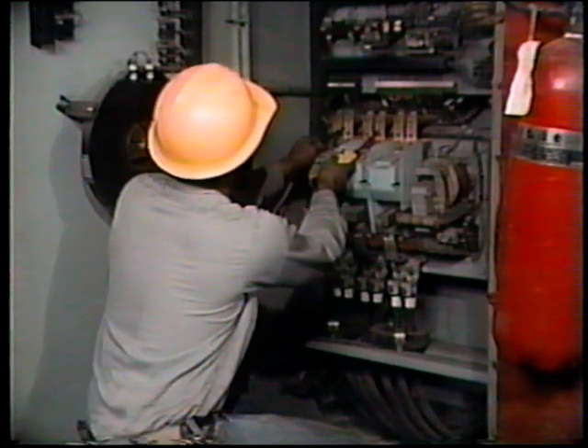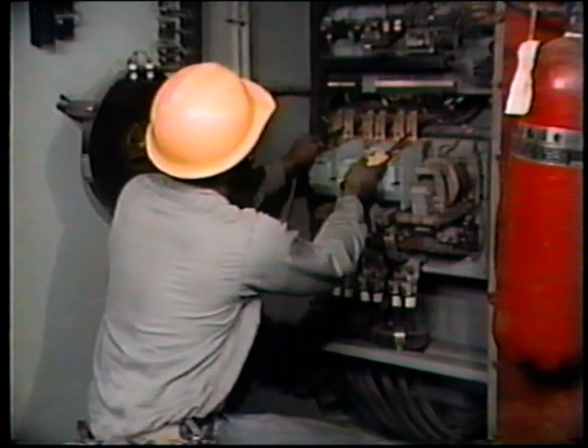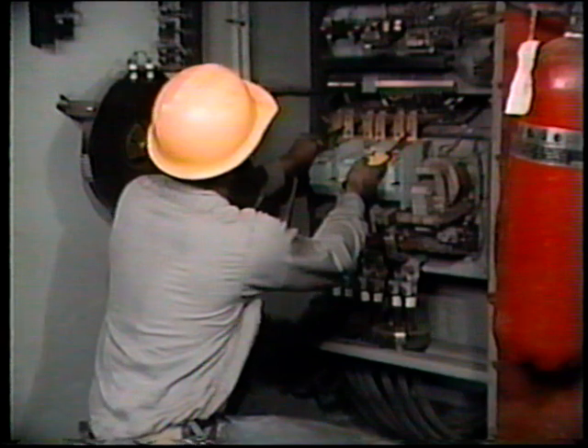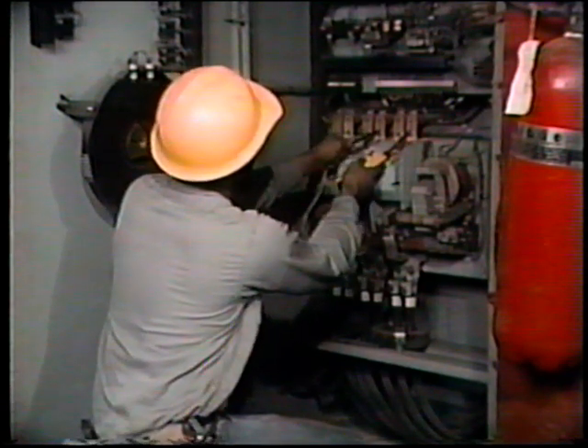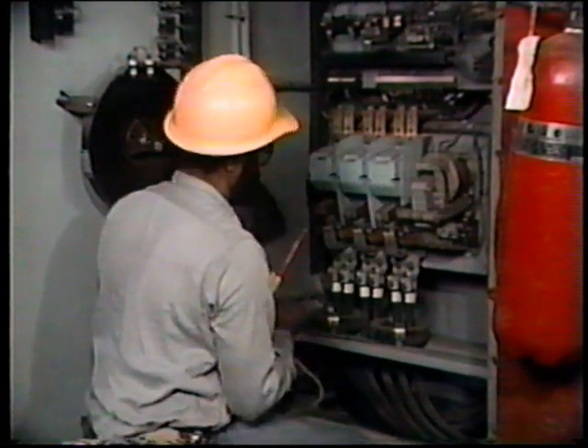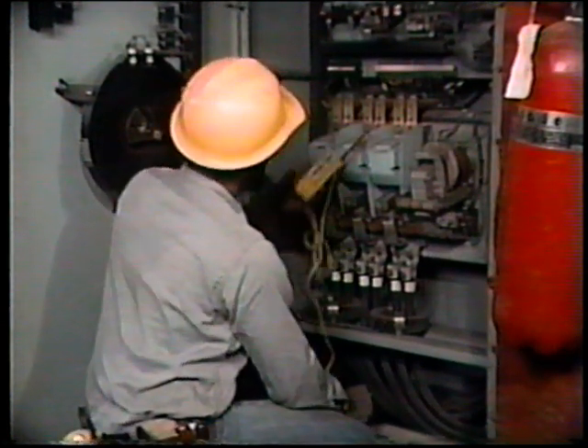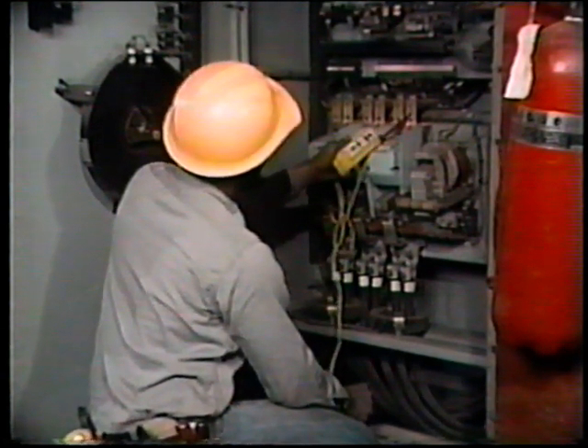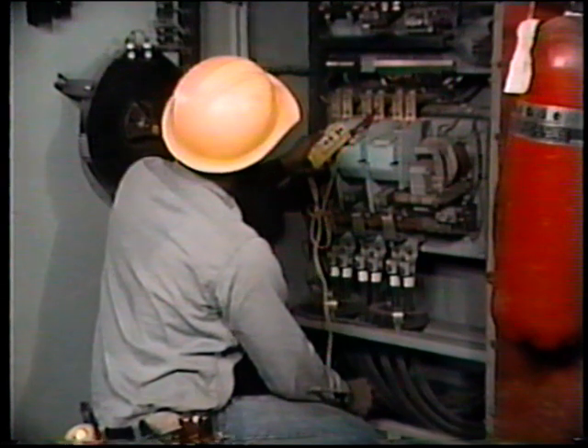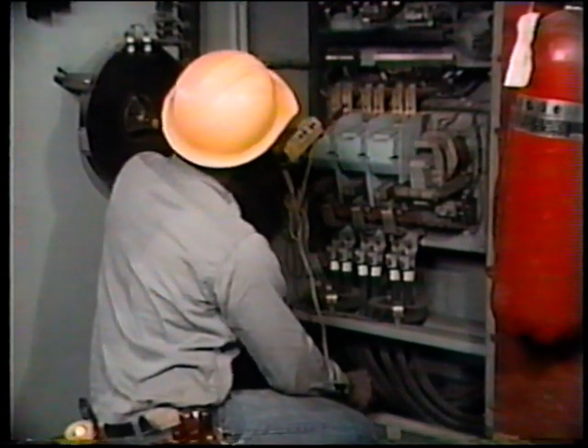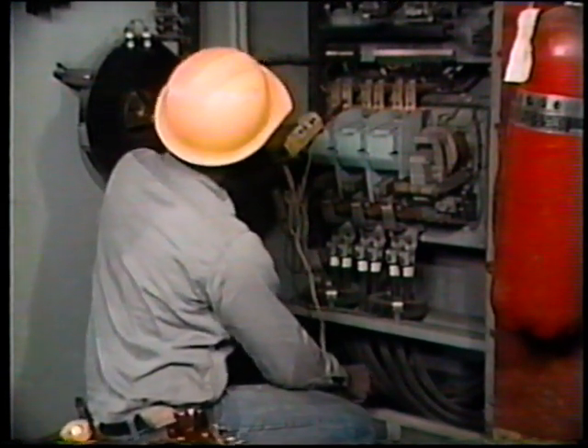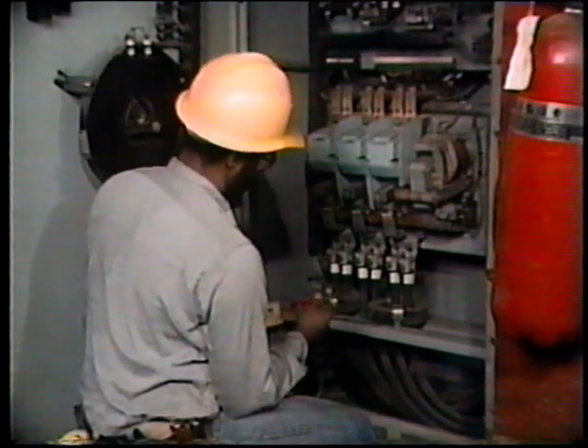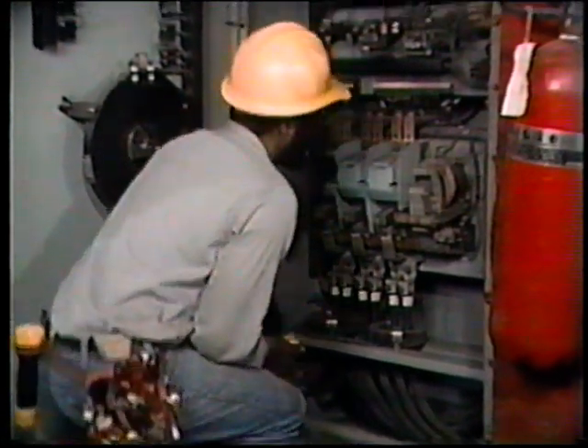Next, the AC power supply leads are tested. Readings are taken between all phases. Then each of the 3 phases are tested to ground. Zero readings for all parts of this procedure indicate that the controller is de-energized and safe to work on. Once you're sure the controller is de-energized, it should be thoroughly cleaned.